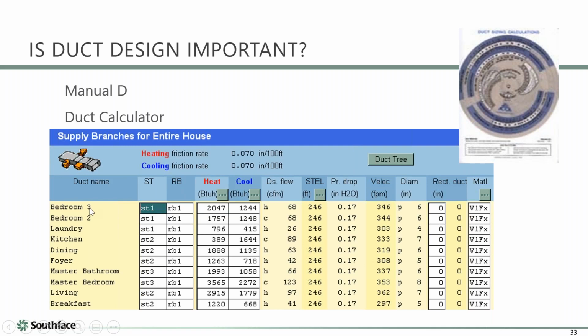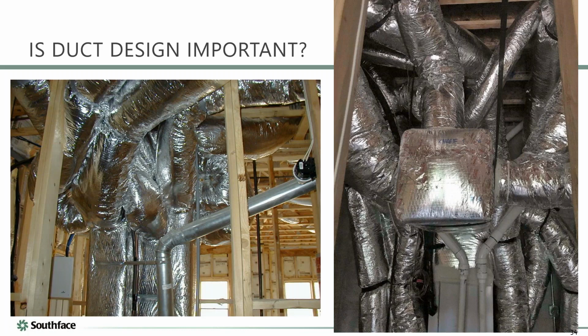And I just thought I'd show an example. Like here, bedroom number 3, its heating load is 2,000. Its cooling load is about 1,200 BTUs. And the heating is the dominant CFM. So you need about 68 CFM. And the software is saying, I think you can do that with a 6-inch flex duct. If you look down here at the kitchen, you can see that the heating is pretty small, 400 BTUs an hour. The cooling is bigger, 1600. Cooling is the dominant load, and you back out and it's almost 90 CFM. So it says, okay, 6-inch is not big enough. You need a 7-inch or an 8-inch with a damper. That's kind of the basic rules of how the duct design process works.